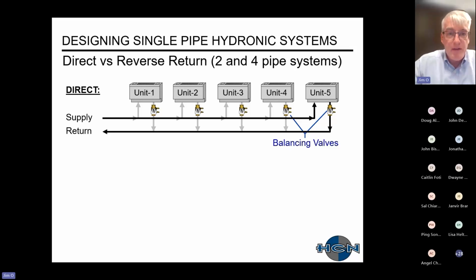For distribution piping, there's two types. There's a direct and reverse return. They can be either in one, two, or four pipe systems. What's depicted on the screen here is the direct system. So if you start on the left with your supply, your supply water travels to the first unit, comes out of the balancing valve, and then returns to the return piping system, and then travels to the left. As you can see, the water that travels from route 1 has a much shorter route than route number 5. So you would need balancing valves to force the water from that first unit down into the fifth one.